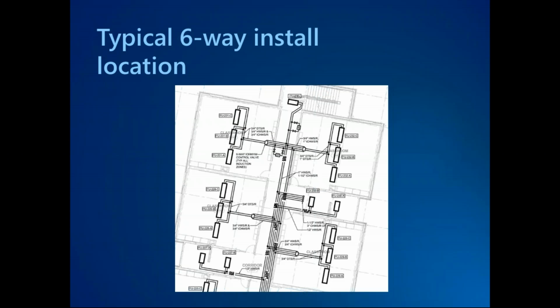So we need to address that with the fact that the 6-way has your supply and return taps perpendicular to your zone taps. So when it comes to a piping design and the install, something to consider is we need to add some other sort of solution.